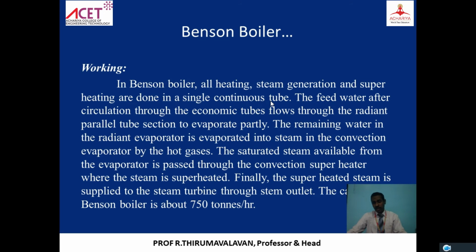One is coming from the economizer, another from the forced circulation pump, another from the air preheater, heated through convection. It goes back to the boiler drum, where the water and steam are separated. There are 3 tubes going in and out. But in the case of Benson, it starts from the feed, and then comes out as steam at the one end. Only one pipe is going everywhere. It enters at one point and leaves at another point. The same pipe is continuous tubes.